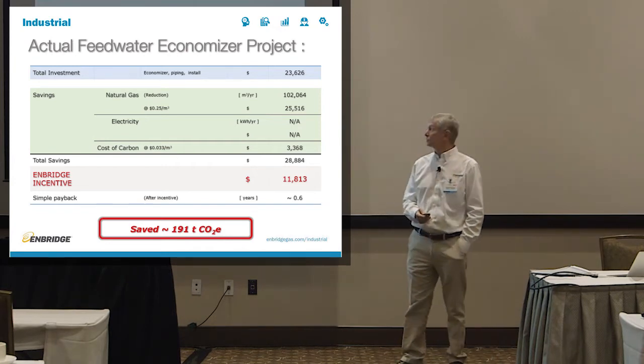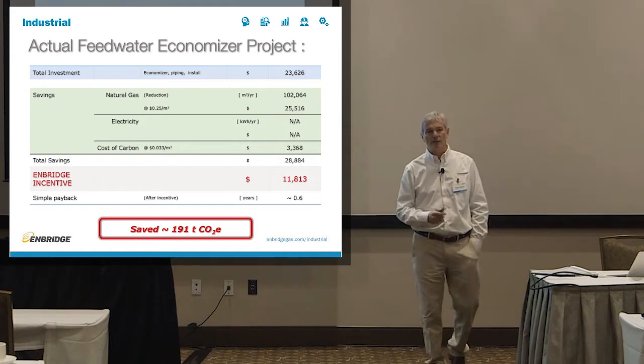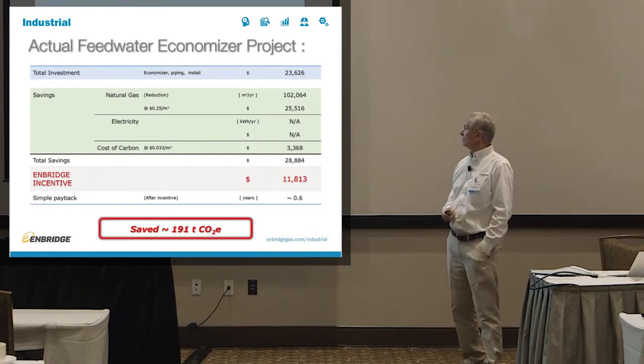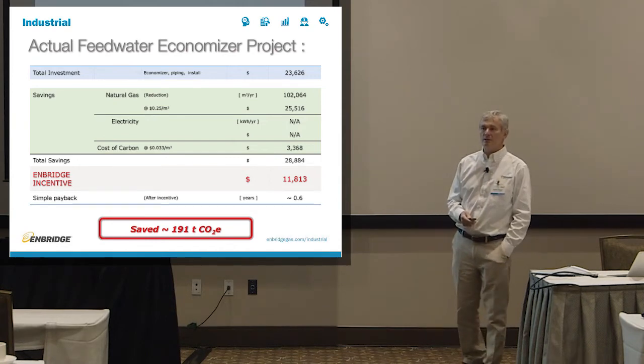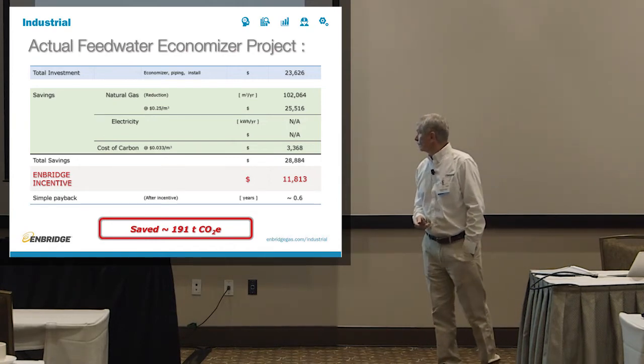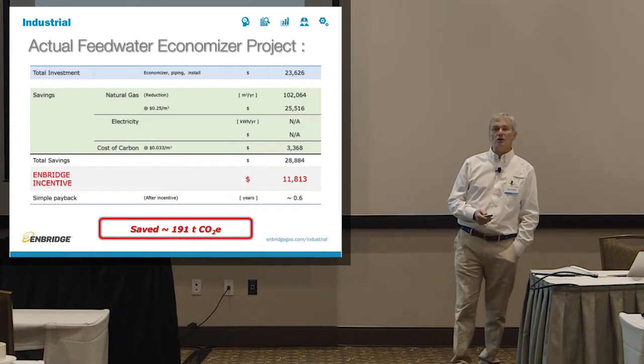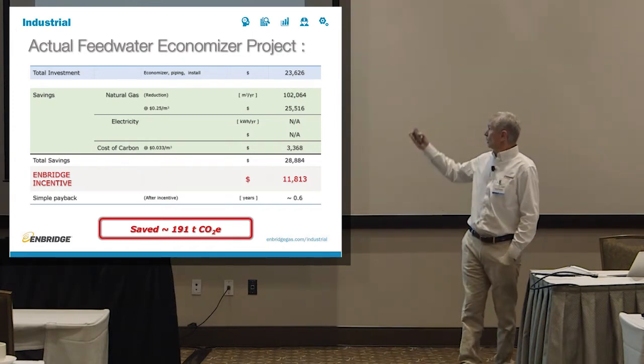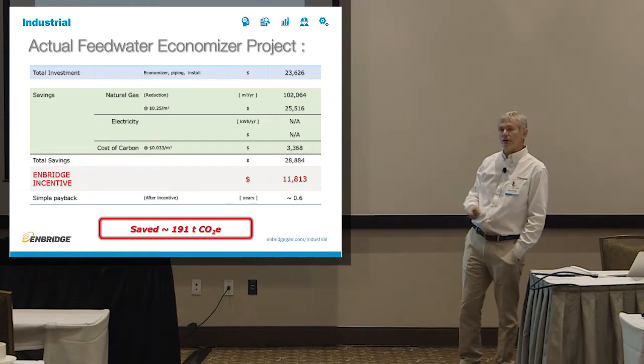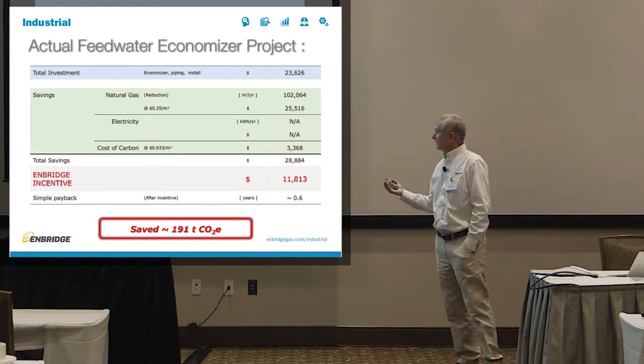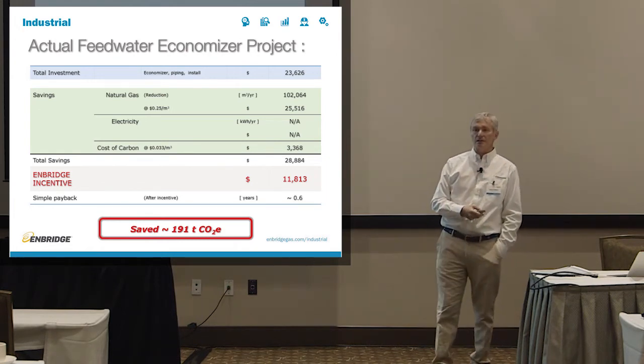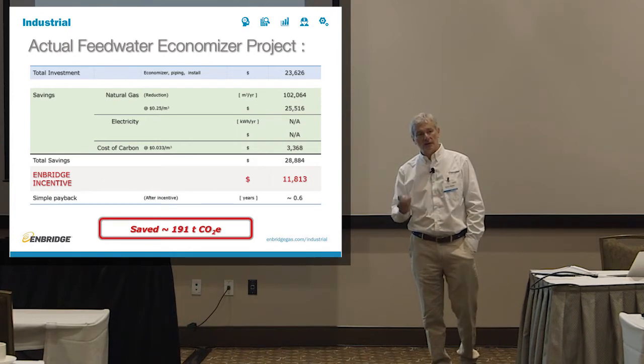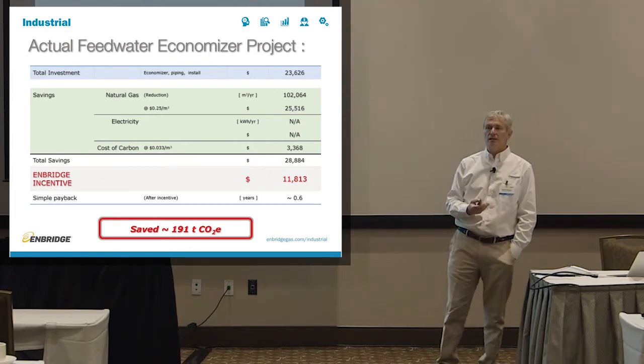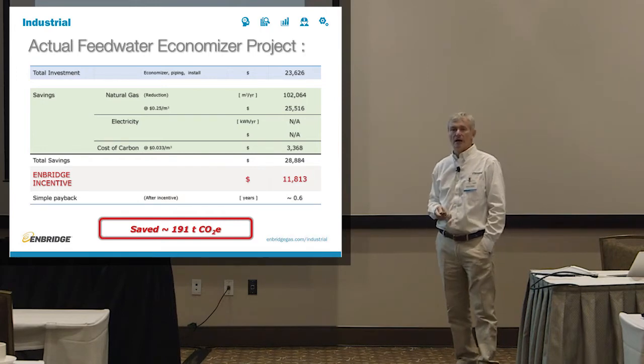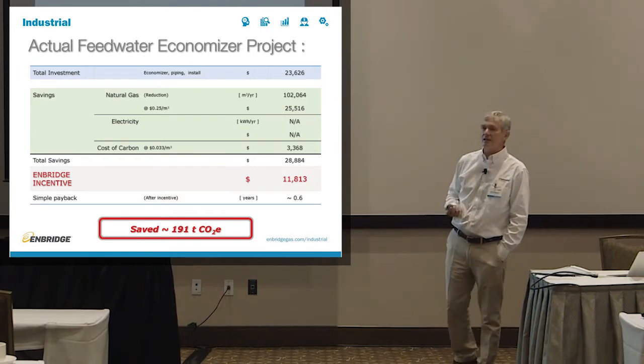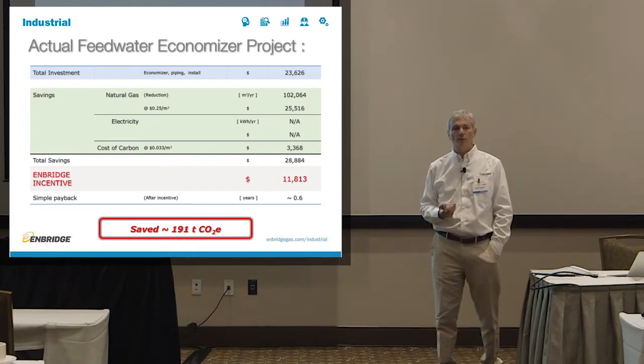Total investment of the economizer install was about $23,626. It saved them about 100,000 cubic meters of natural gas. And we gave them almost $12,000 incentive. So their cost was actually almost half that. So for about $12,000 investment, they have gotten back 100,000 cubic meter savings every year. $29,000 every year of savings for $12,000 net investment. Payback is about half a year. And by doing that, they saved 191 tons of CO2 equivalent.